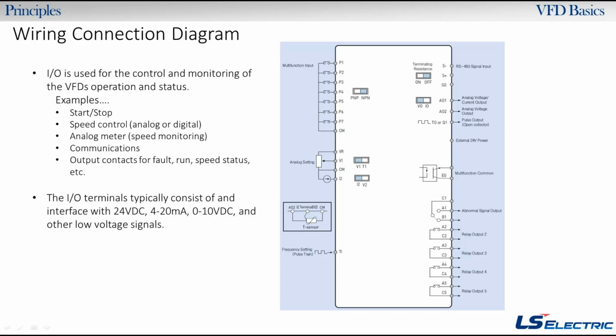So the control wires, or the control terminals on all drives, so this goes across the board in general, is the I/O, or the inputs and outputs. They're used for controlling and monitoring the VFD's operation and status. For example, your start-stop. If we look over here, this is a wiring diagram for an LS drive. There's P1, which is a forward run, and P2, which is a reverse run. If you have a contact closure on P1 or P2, it's going to run forward or reverse. That's one of the most common things you'll need to get a drive started besides your main three-phase or single-phase power input.